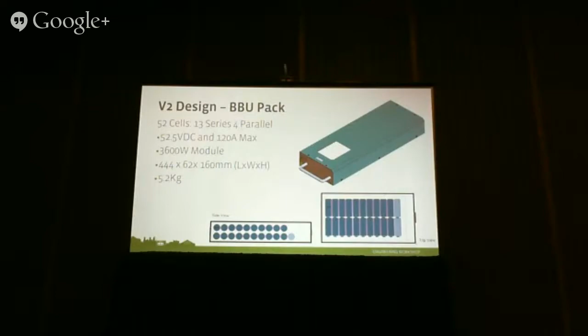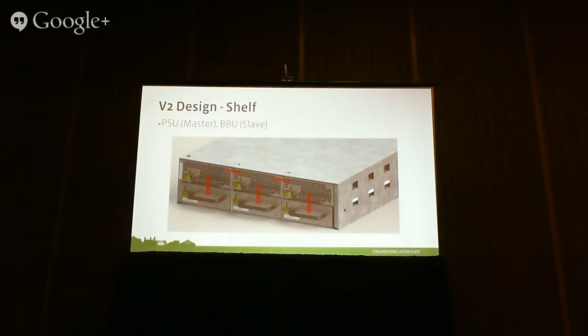The shelf, we looked at this picture in previous presentations. It's a master and slave setup between the power supply and the BBU. The power supplies can talk to each other, but the BBUs can't, and the BBU only corresponds to an individual power supply. So if the power supply fails, you lose access to that BBU because the power supply was the master. On the rack side, there are 2 shelves, 6 power supplies, and 6 BBUs, all completely separate from each other.